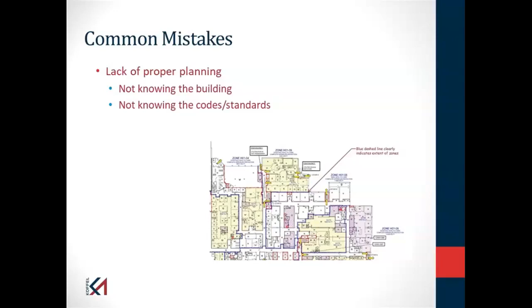Integration of systems: years ago we had standalone, fairly simple fire protection systems. Today we've got smoke control systems integrated with the fire alarm system, because it's the detectors that actuate the smoke control system. It needs to be integrated with other HVAC systems in the building that might impact its performance. If I don't properly integrate those systems, the actual outcome may not be what we desired.